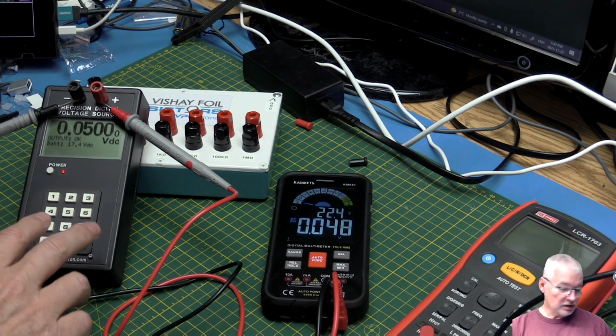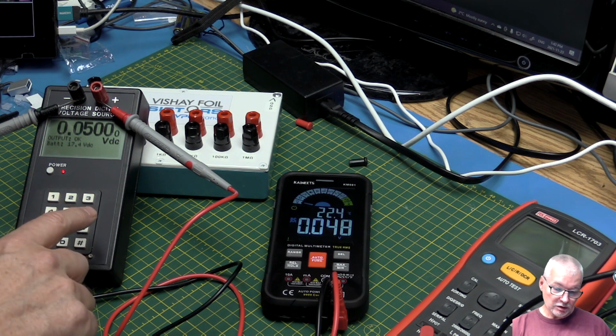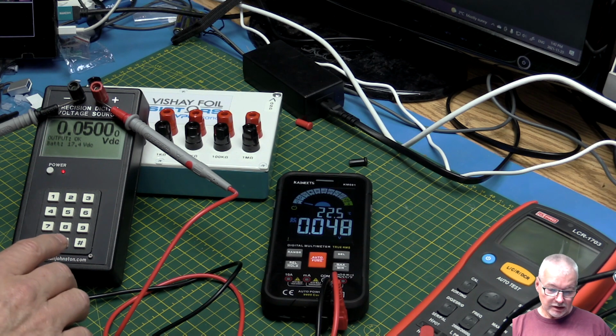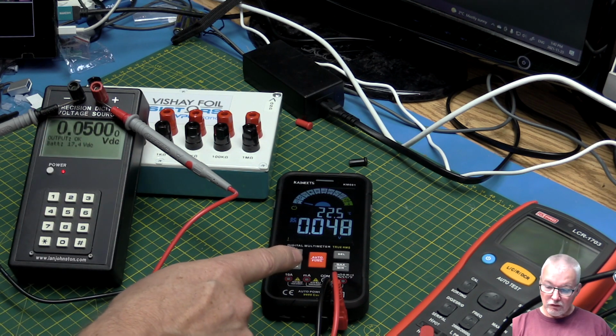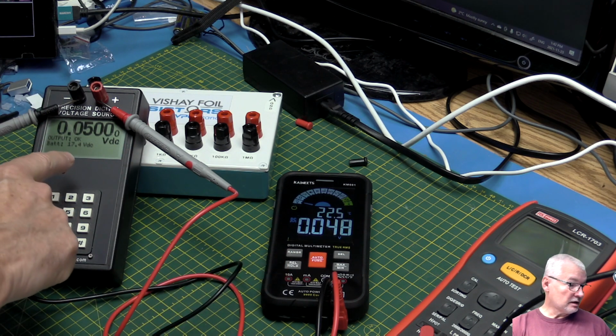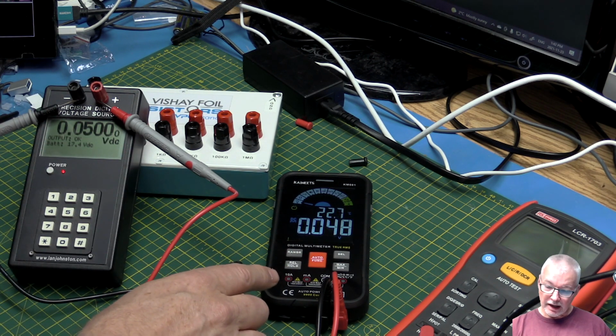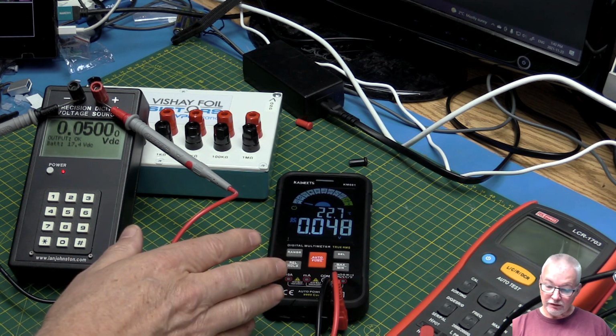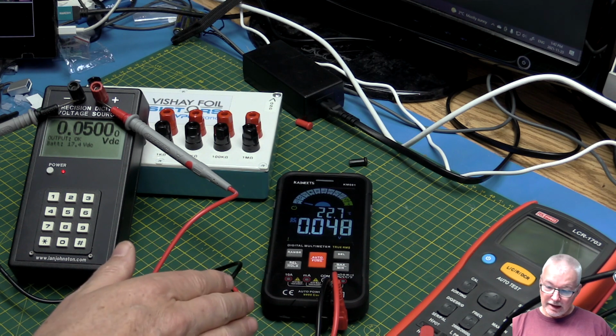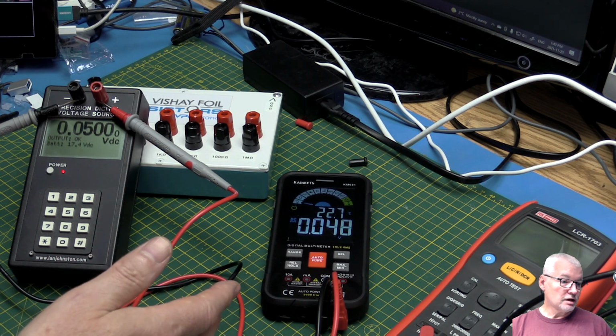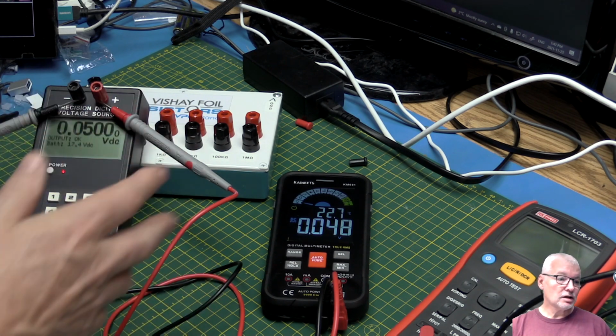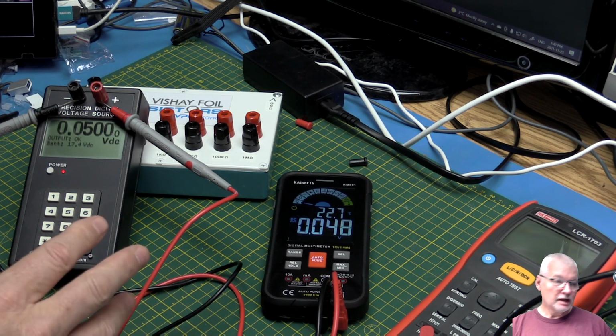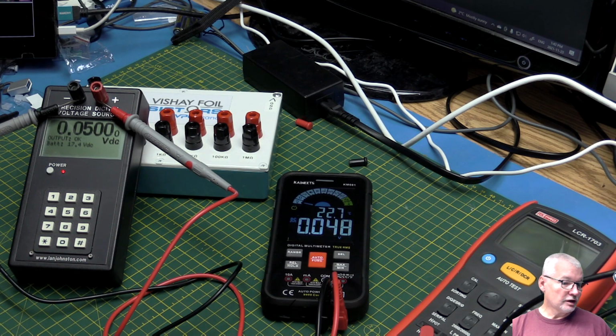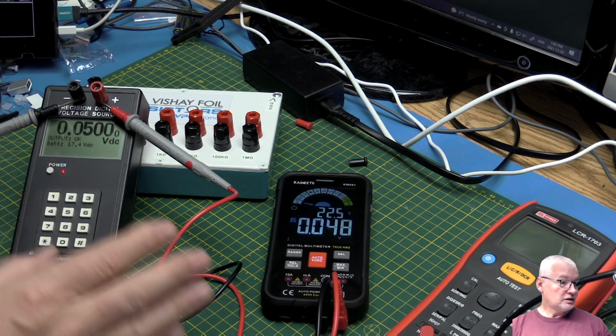This is a very, very precise reference standard. You can dial in any voltage up to 10 volts. What I'm going to do is check the meter for accuracy. I know this is spot on, so we'll check the meter against it. This only goes up to 10 volts for the voltage checking, which for most bench use is more than enough. We'll check some mains type measurement shortly, but that's an area that I don't normally delve into with my tutorials or reviews, because I don't want to encourage younger people to be sticking things into mains receptacles and stuff like that. So anyway, let's get on with the measuring.